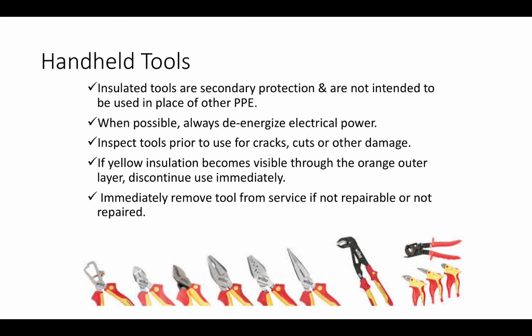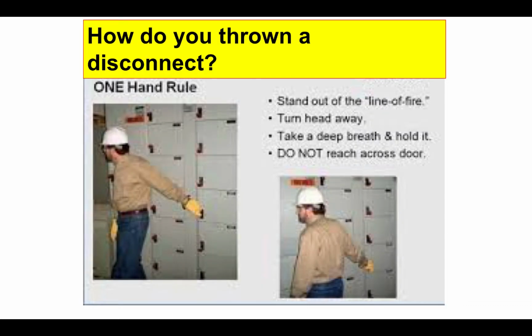Immediately remove any tool from service if it's not repairable or not repaired. If you end up throwing disconnects as a part of your work, there's a one-hand rule that applies. Stand out of the line of fire, turn your head away, take a deep breath, and hold it before you turn that disconnect on. Do not reach across the door. This is because it could have an arc flash or a major spark inside, and can sometimes actually blow apart the container.